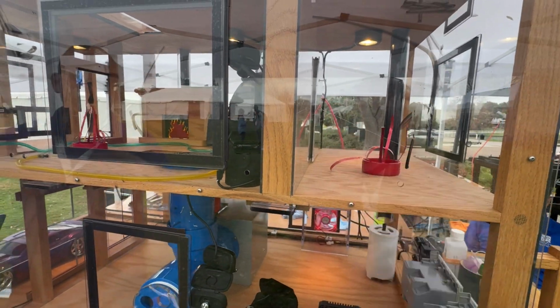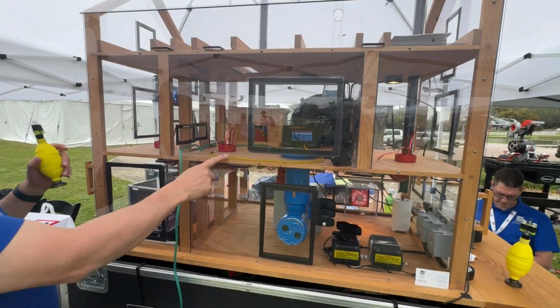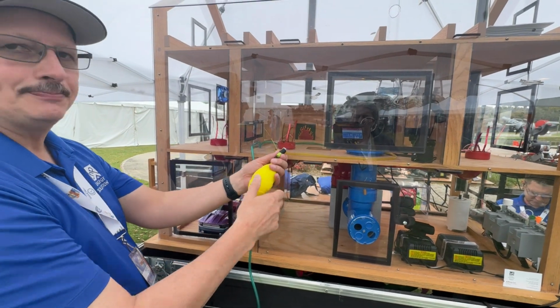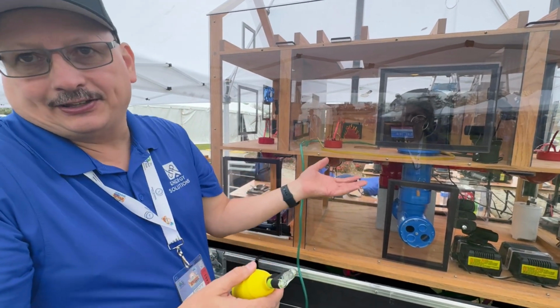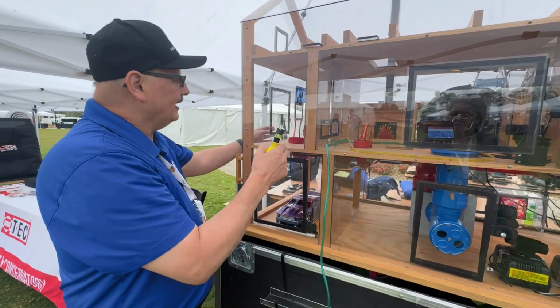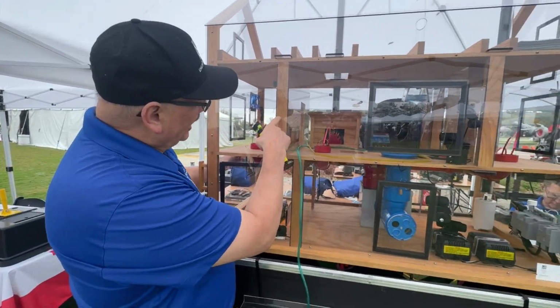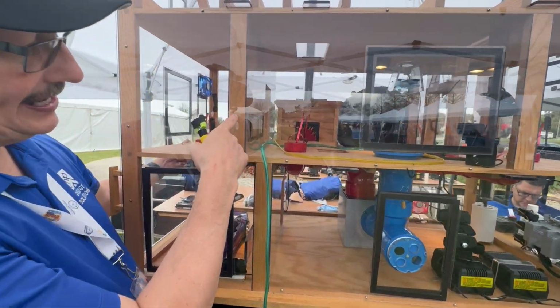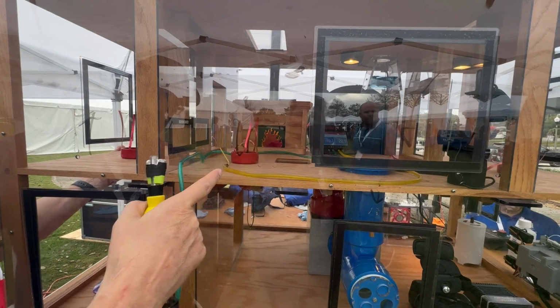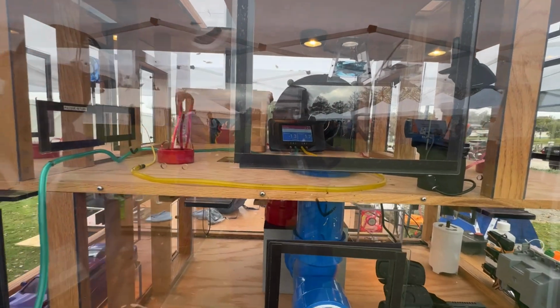So this room is probably going to be hot and stuffy. Anywhere there's holes to the outside, it's pulling air in—kind of like the duct leakage stuff we were talking about. But watch, I'm going to open this door just a little, and as I open it, you'll see both of those numbers move closer to zero.